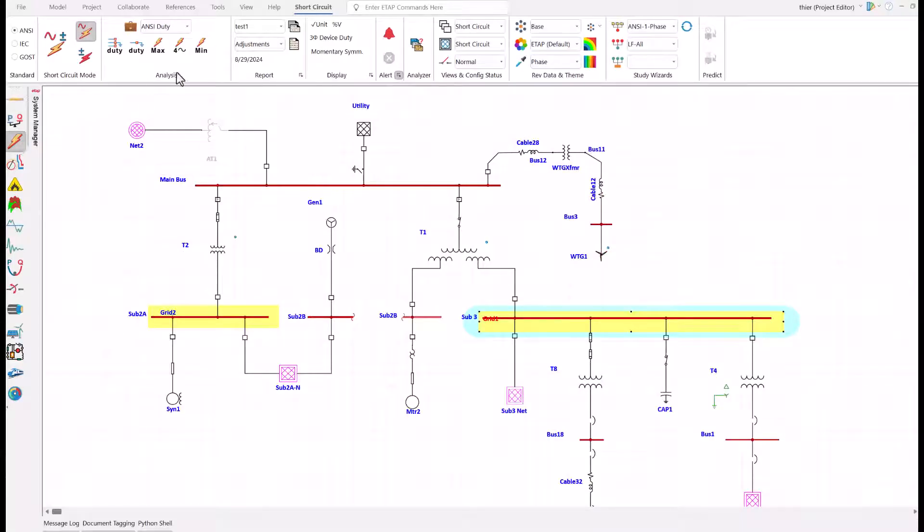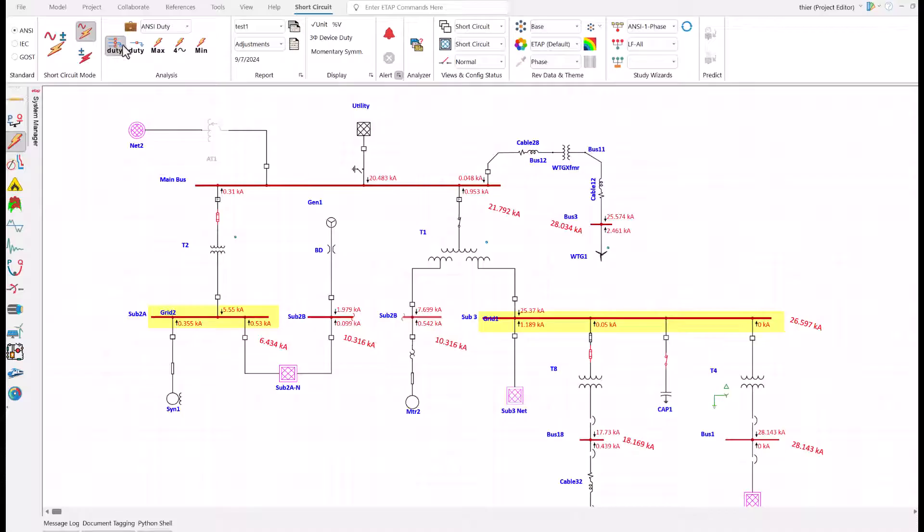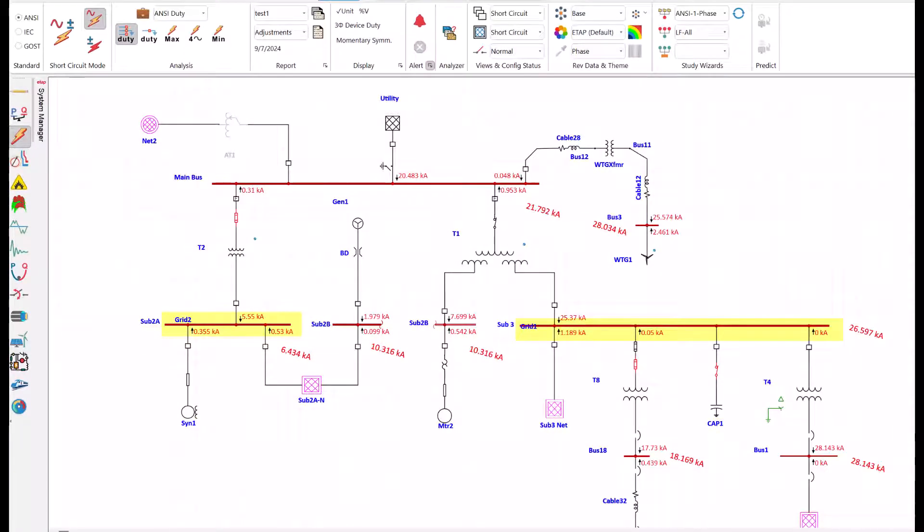Short circuit. Now we will run short circuit three-phase device duty. Instead of reading the report, we will highlight the result here on the ETAP one line. This is where another cool feature of ETAP shines: data blocks. This short circuit view shows several results. I have an arrow showing momentary symmetrical fault currents. However, it does not yet translate to my audience. Are those currents telling me something? Is the facility rating adequate for short circuits? Is it inadequate? I cannot confirm from this.